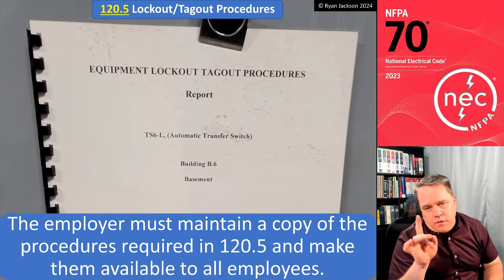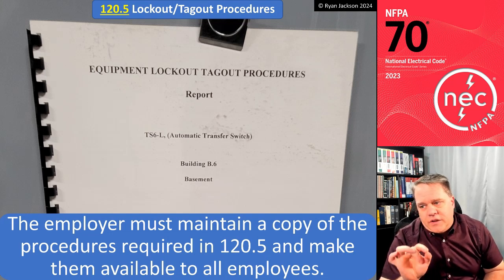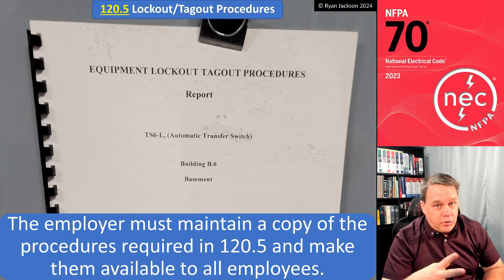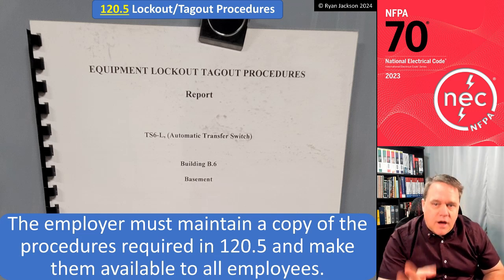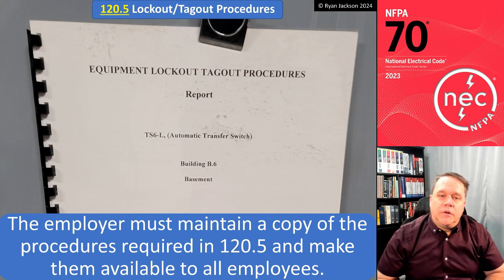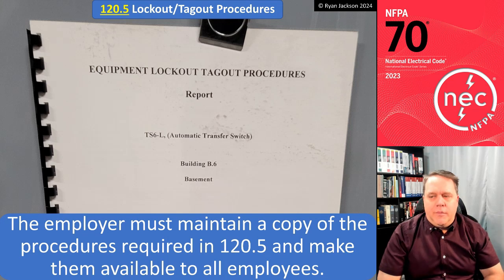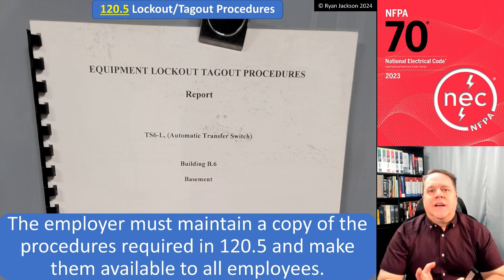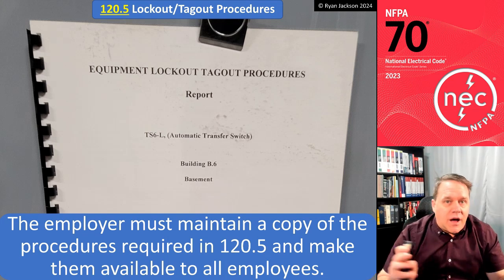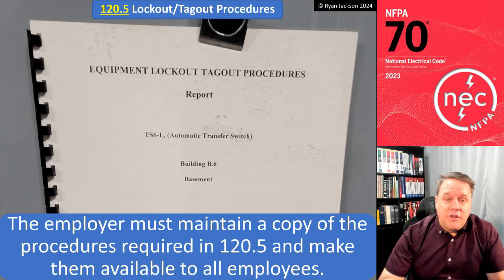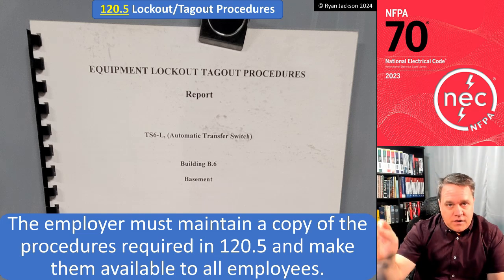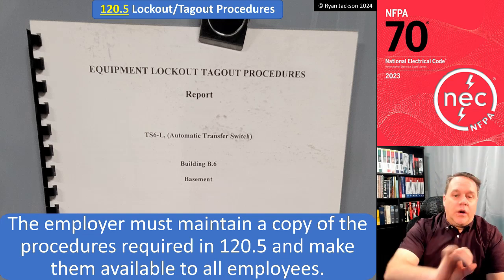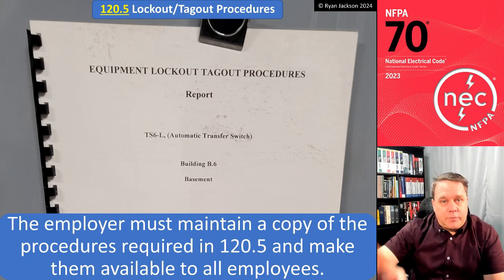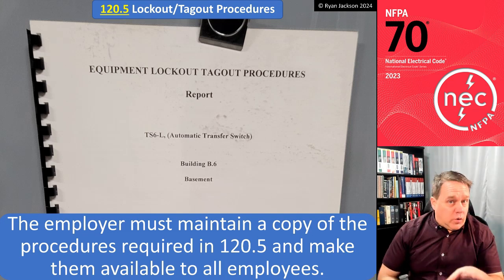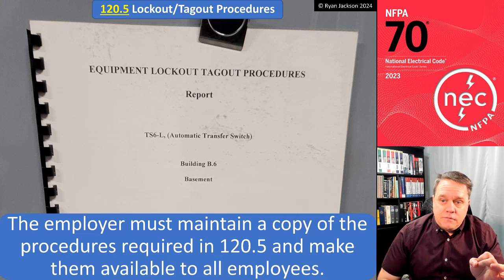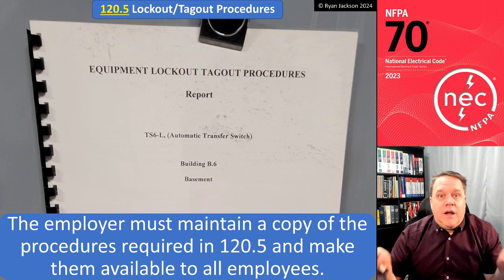All right, this example that I'm showing here in the photograph, this was at a hospital that I was fortunate enough to go on a tour of, and they had the lockout tagout procedures for each individual equipment printed and attached to all the different equipment. Awesome. I mean, outstanding job. Unfortunately, that's probably not how most places are. I wish that was the case. But for this, it actually told us exactly what needs to be shut off, how we can verify it, where to put the lock, where to check the voltage, right? They printed it out and put it on each individual equipment. If you work at a facility and you're able to do that, do it, right? Make everybody's life better and safer.